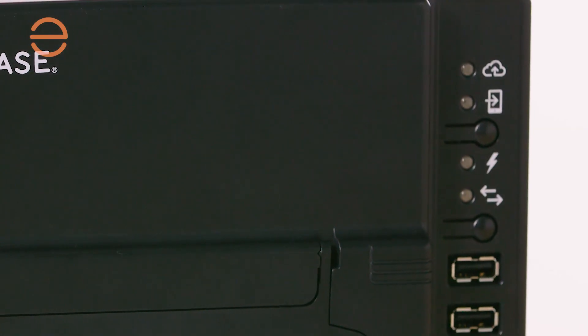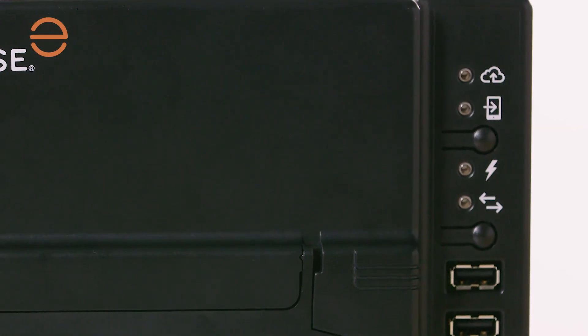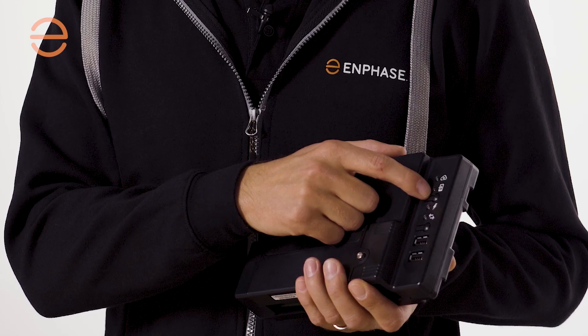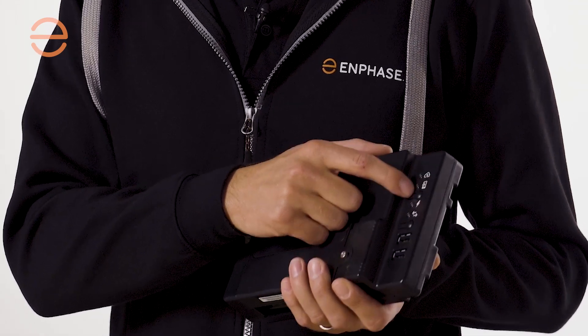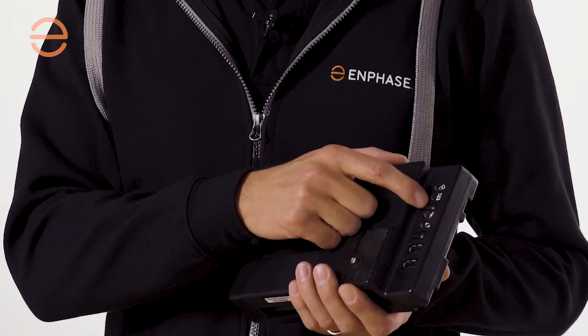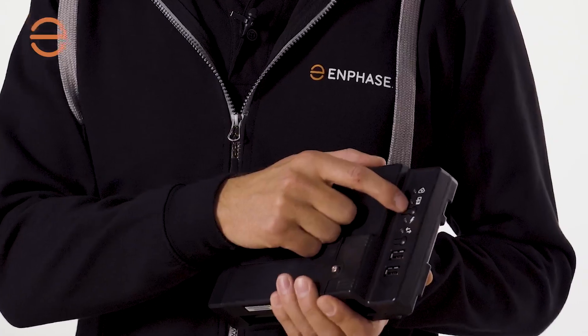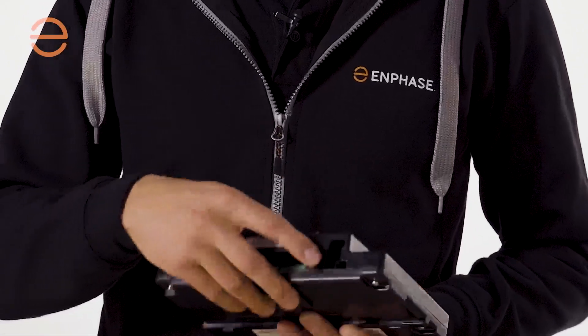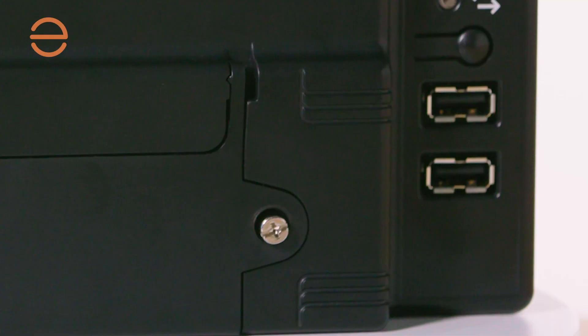The two buttons have multiple functionalities. The topmost button, if pressed once, activates the access point. If you hold this button, it will activate WPS, but only if you don't have an ethernet cable connected. The bottommost button is used for the PLC scan for everything before the iQ 8 microinverter series.